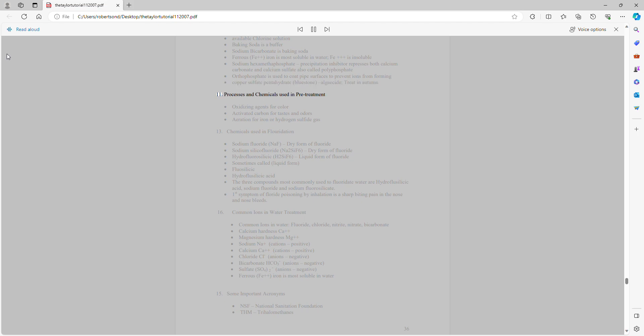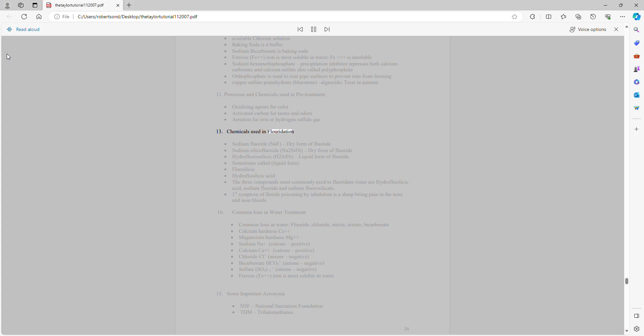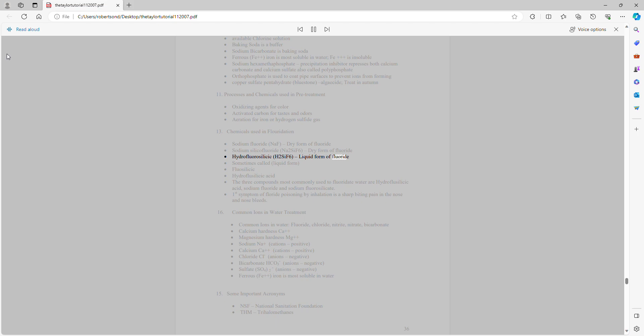Processes and chemicals used in pretreatment: oxidizing agents for color, activated carbon for taste and odors, aeration for iron or hydrogen sulfide gas. Chemicals used in fluoridation: sodium fluoride (NaF) — dry form; sodium silicofluoride (Na₂SiF₆) — dry form; hydrofluorosilicic acid (H₂SiF₆) — liquid form, also called fluosilicic or hydrofluosilicic acid.